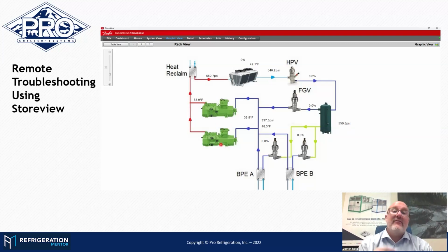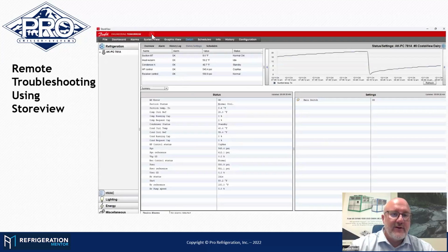Like, I'm off. What I do like with the graphical side is when it goes into an alarm condition, if there is one present, all of these values will highlight red. So it's a very distinct, like, hey, why is this all glowing red right now? Something's wrong. Even though the system might be running and operating, it'll still stay red if there's an alarm condition present. So I do like that. Yeah. This is a kind of even a further level or another layer of view. And so you go from the system view to the graphic view over to the detail view.